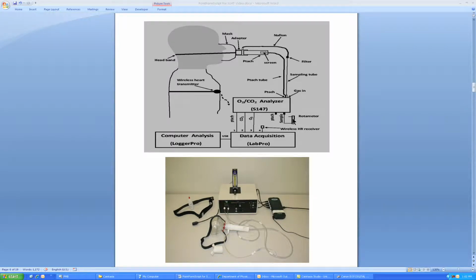The rotameter or flow meter is connected to the sample vent at the back of the S147, with the line going into the bottom of the rotameter. This allows us to monitor the sample flow, which should be 300 mils per minute. If not, the pump speed can be adjusted by the pump speed control to make the flow 300 mils per minute.